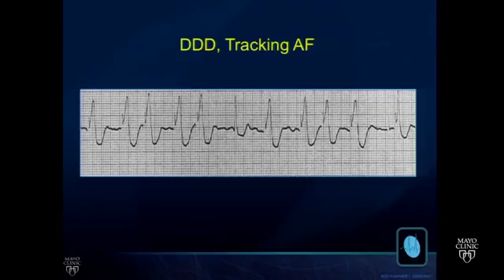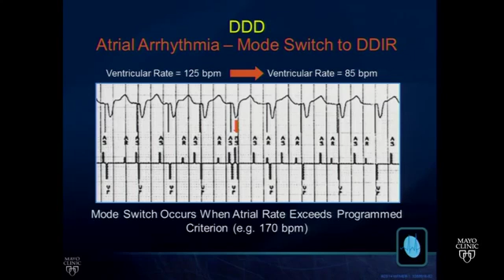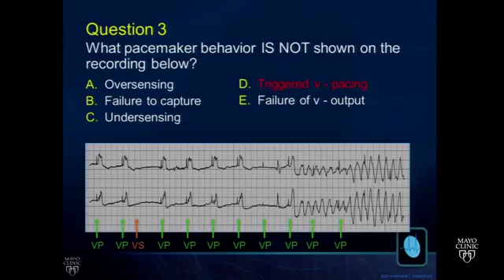So the way we deal with atrial fibrillation in dual chamber pacemakers is the so-called mode switch algorithm. If the atrial rate is faster than some arbitrary number, 170 beats per minute, the device concludes that an atrial arrhythmia is present, and it reverts to that backup DDI or VVI mode of operation. Okay, that is a complicated strip.